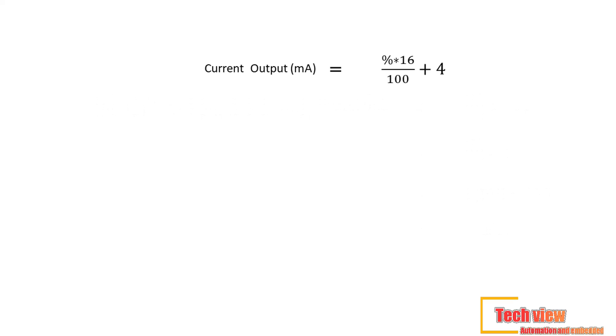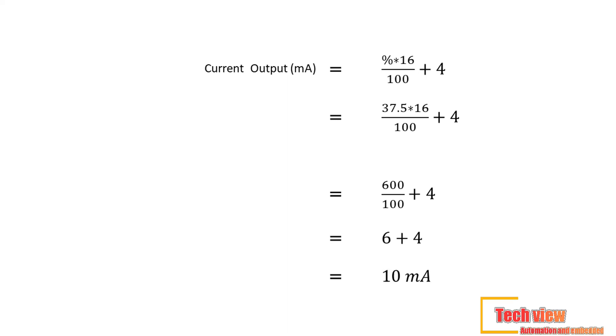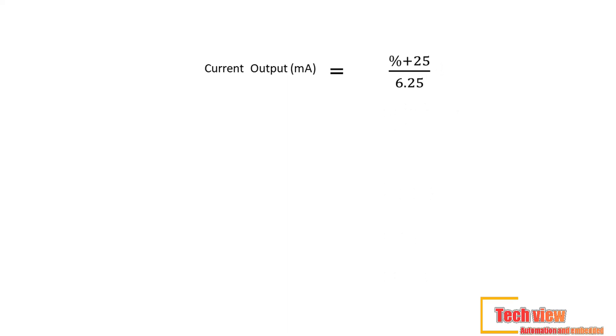Now let's apply this value to our current conversion formula: 37.5 percent times 16, divided by 100, plus 4. That equals 600 divided by 100, plus 4, which means 6 plus 4. So the result is 10 milliamps. Now we can find the milliamps output.